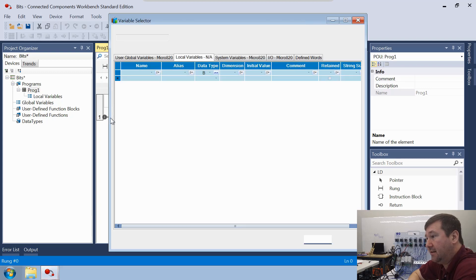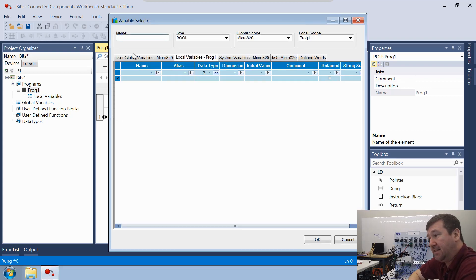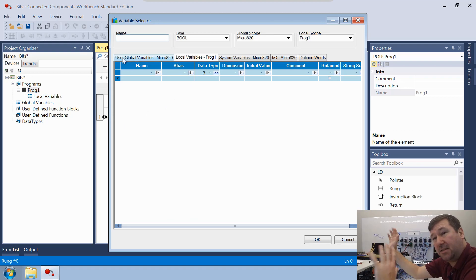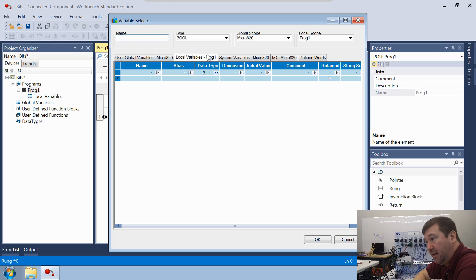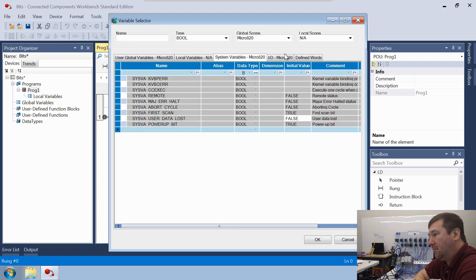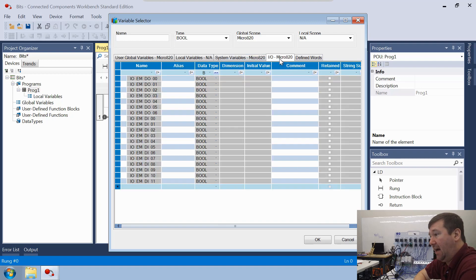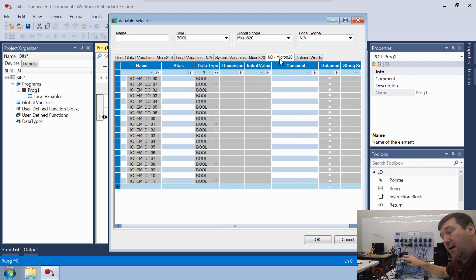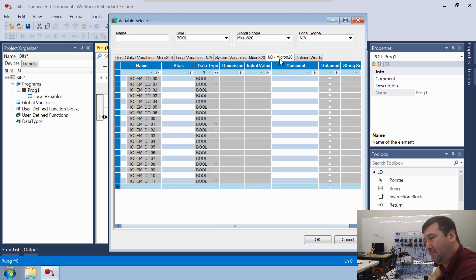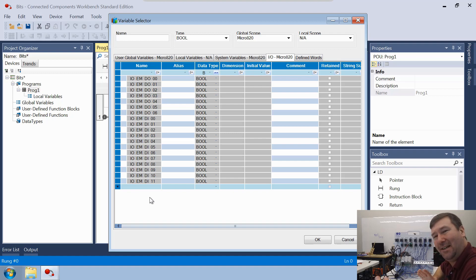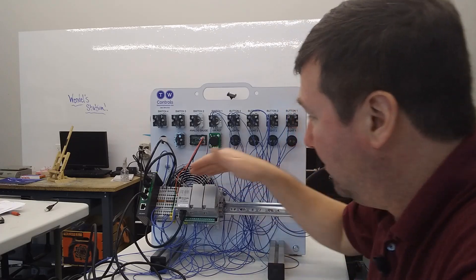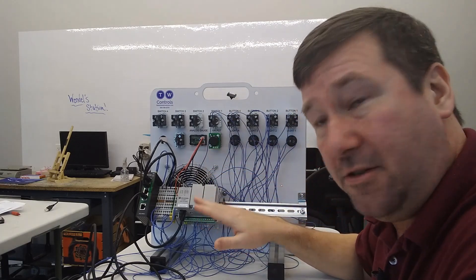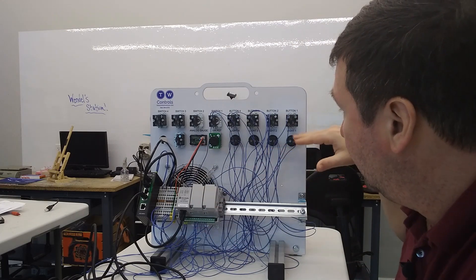We'll bring it down and that'll bring up our Variable Selector. You have global variables accessible from any program, local variables only accessible from this program, and the one we're really going to be focused on today is the I/O tab — this is the physical I/O of our Micro 820. One thing that stumps me often is that the digital outputs are above the digital inputs. So make sure you pay attention to where it says DI or DO. The DI is the digital input — those are all the buttons wired to the top. The DOs are the digital outputs, which are what you wired to the lights.